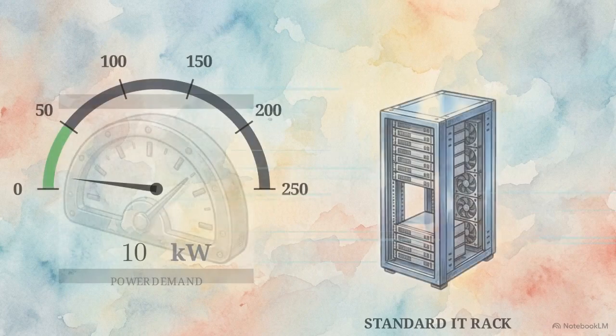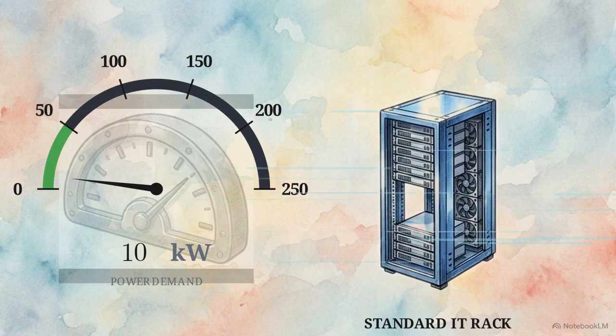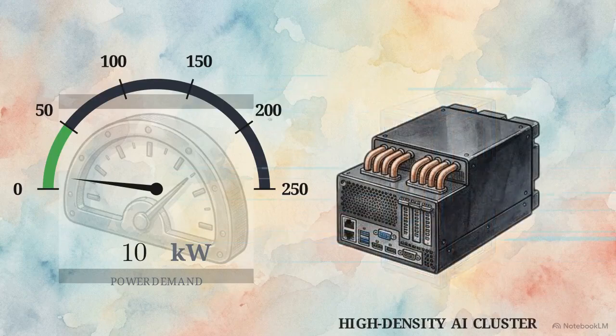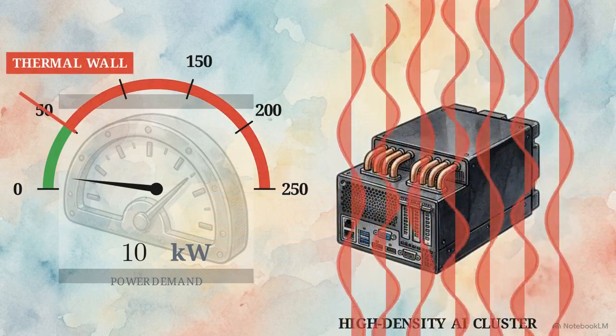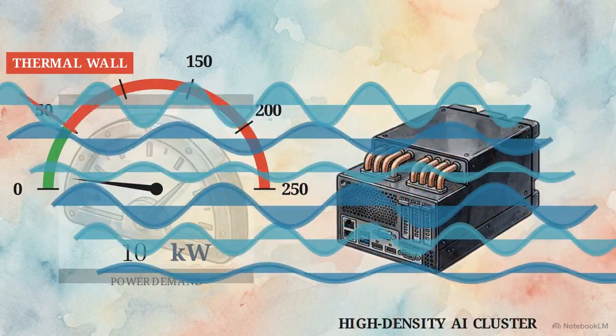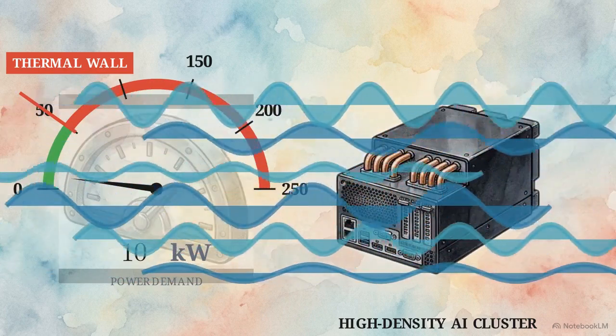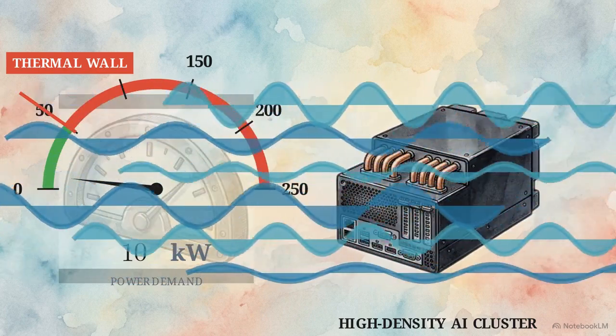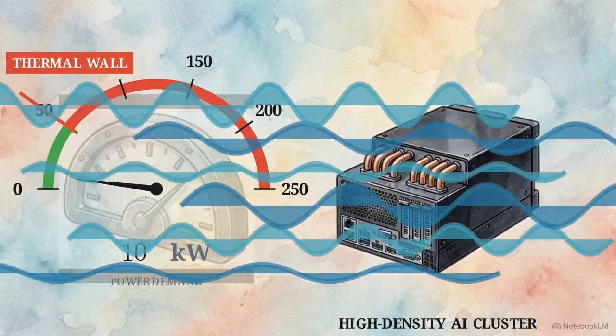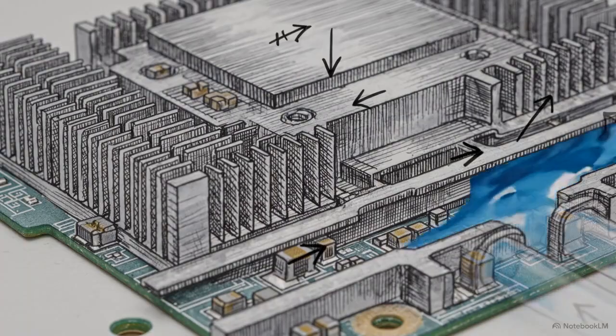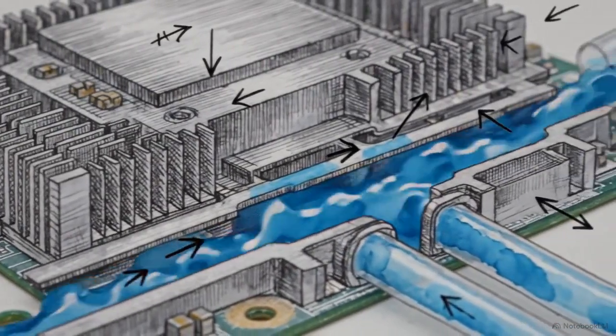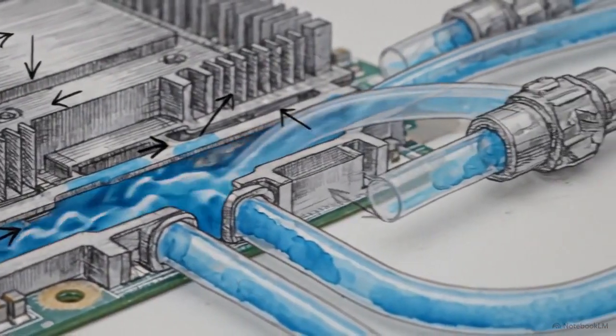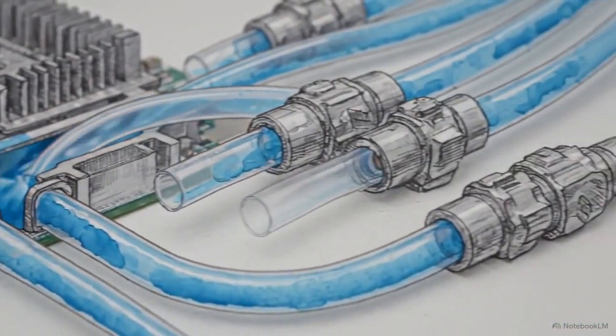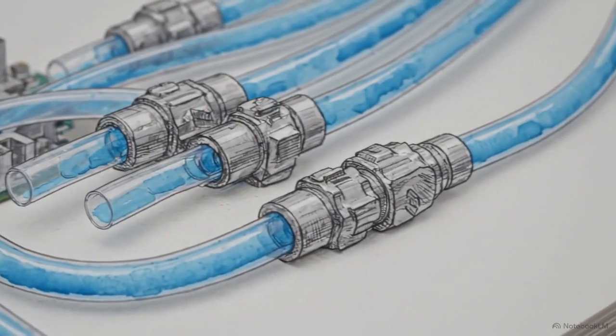This scale shows power demand rising from standard IT racks at 10 kilowatts to next-generation AI clusters that redline at 250 kilowatts per rack. Passing 50 kilowatts hits the thermal wall, where air cooling no longer has the thermal capacity to dissipate heat. Advanced liquid cooling, whether implemented as direct-to-chip solutions or full immersion tanks, has become a strict engineering prerequisite for modern high-density enterprise AI deployment.